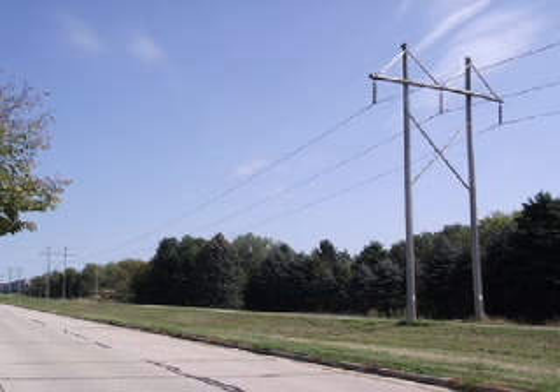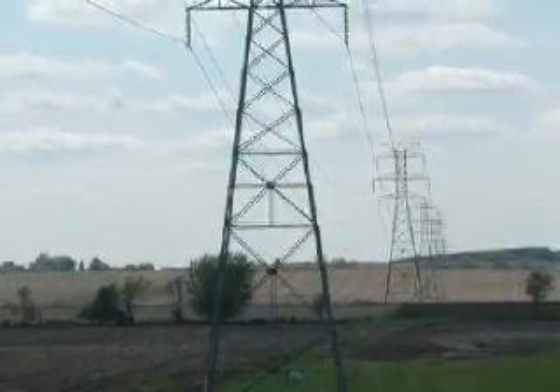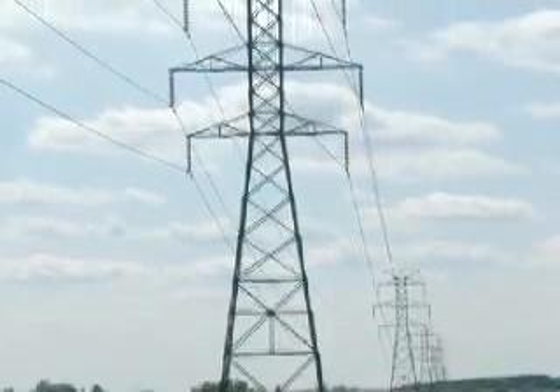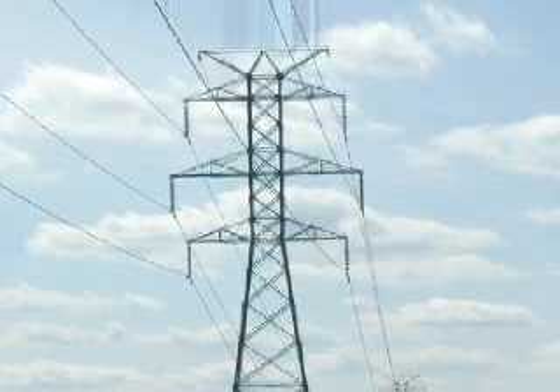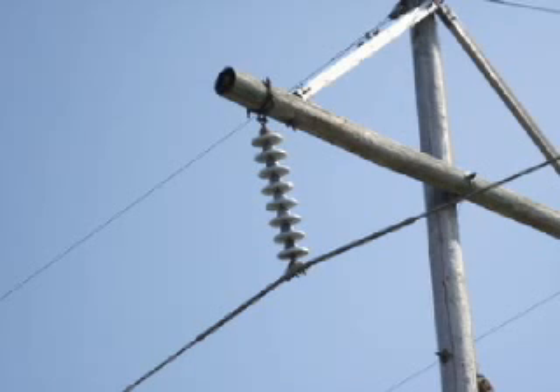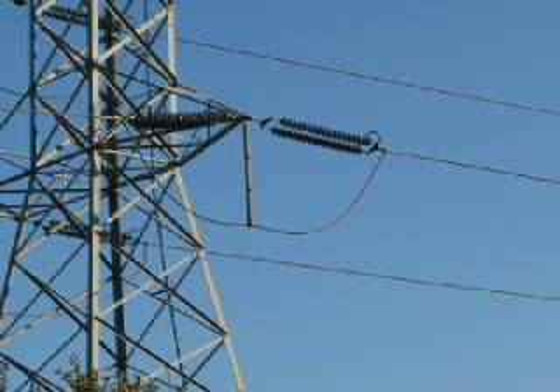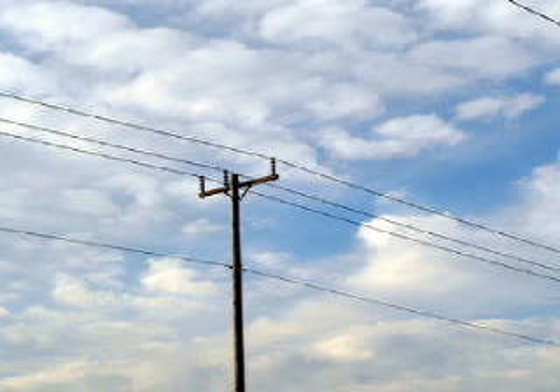Overhead transmission lines are different than the smaller distribution lines that are owned and operated by local electricity companies. Although all electric lines can pose significant hazards to anyone working around them, transmission lines carry higher voltages, which require more care to ensure that the work is accomplished safely. Overhead transmission lines can be distinguished from distribution lines by the long insulator strings that suspend the wires. The longer the string of insulators, the higher the voltage of the transmission line. Lower voltage distribution lines have smaller insulators and are usually on single-pole structures.